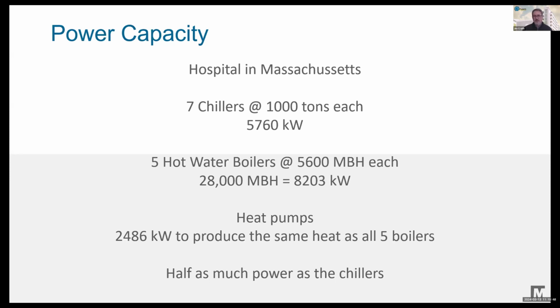So about half as much power as the chillers are taking. And the point of that is if we have enough electrical infrastructure to power those chillers, we have enough electrical infrastructure to power heat pumps, heat recovery chillers to do the same work. Now, you still have to have a source for heat. Heat pumps have to move heat, they can't make heat. So there are other issues here. But generally speaking, if we can find a source of heat, we can drive those heat pumps with the equipment, with the electrical infrastructure that we already have in place.